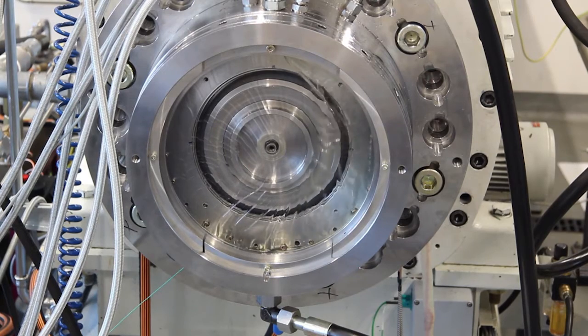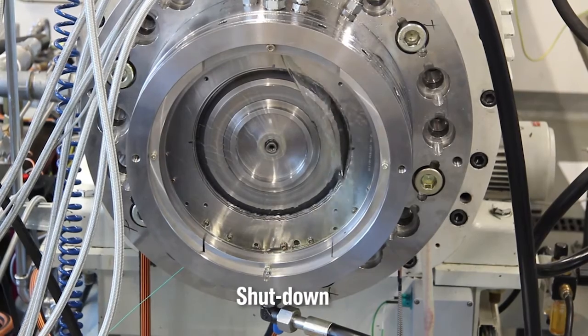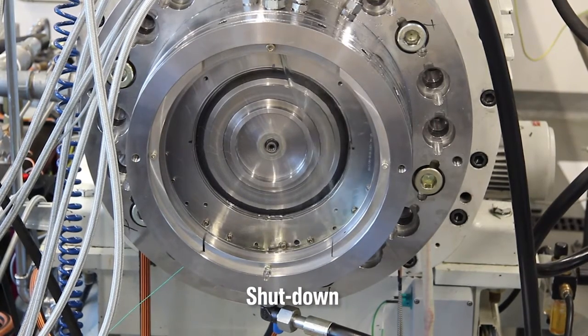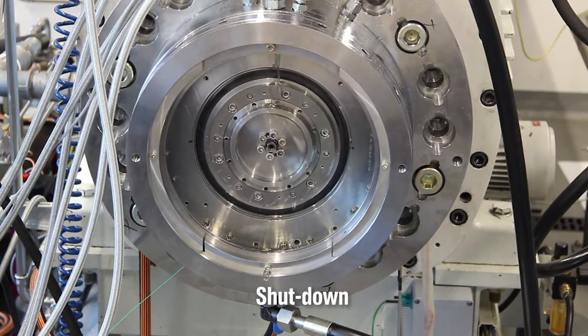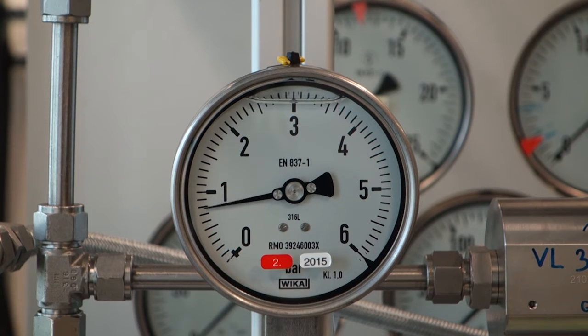As the shaft slows down, the COBA seal remains non-contacting right to the slowest speed range. The test rig is shut down until stationary. In static operation, the COBA seal can be operated unpressurized as demonstrated by the following test sequence.